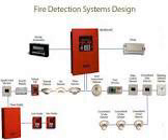So this is giving an alarm when the temperature is 70 degree. It can happen when the fire is a slow one. And it can give an alarm much earlier than 70 degrees if the fire is rapid and the pressure inside increases suddenly, so suddenly that the bleeding is not able to take out the pressure. Yes? So that will be giving an alarm, maybe much earlier than 70 degrees, maybe at 50 degrees. Yes? Makes sense? So this is our heat sensor, heat detector, whatever you call it. One of the elements of fire, that is heat, can be recognized by this one. Will give you an earlier signal.